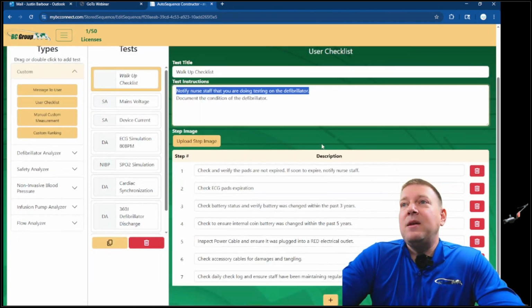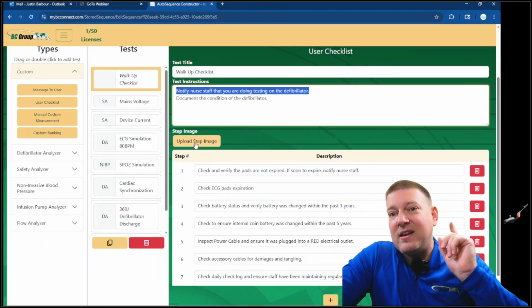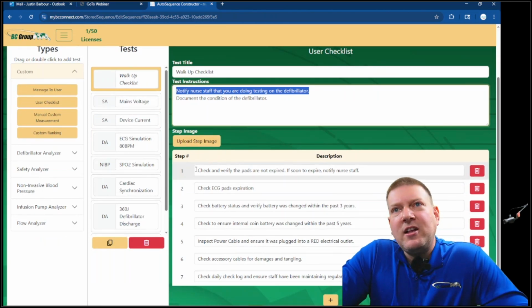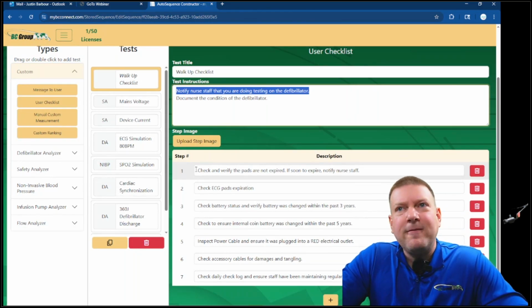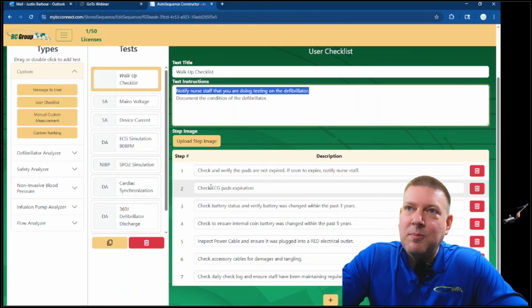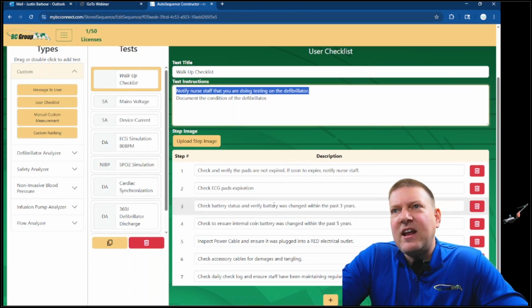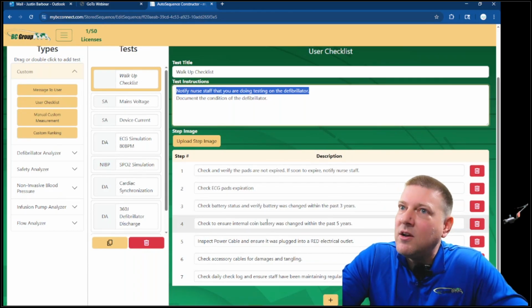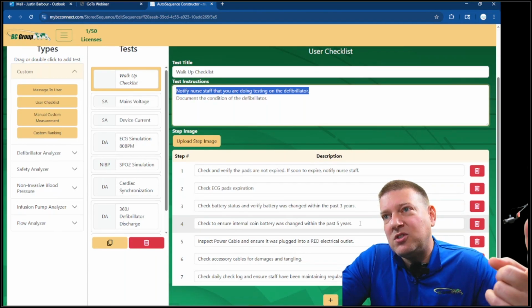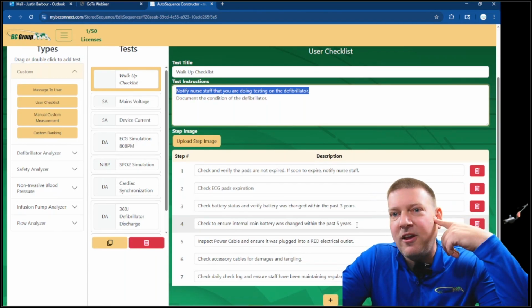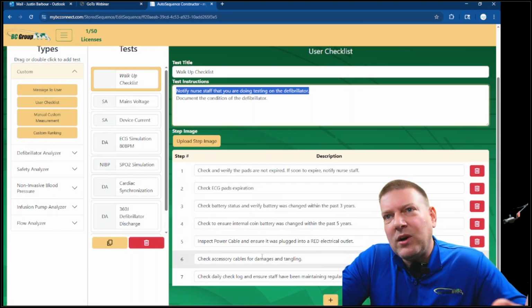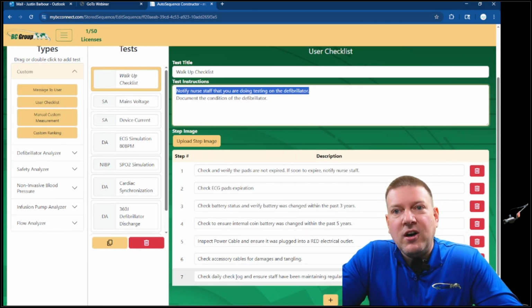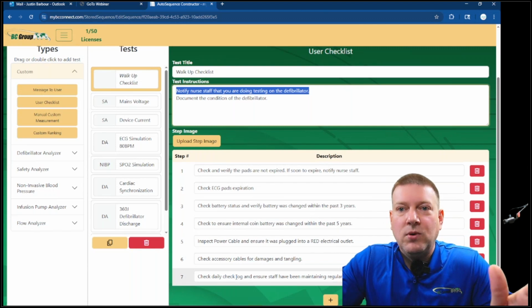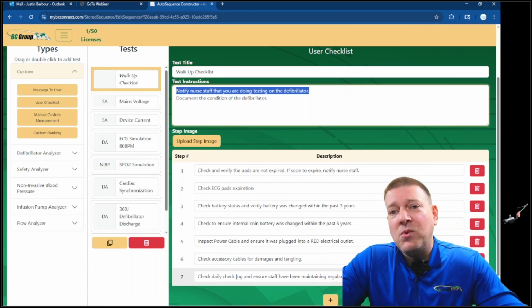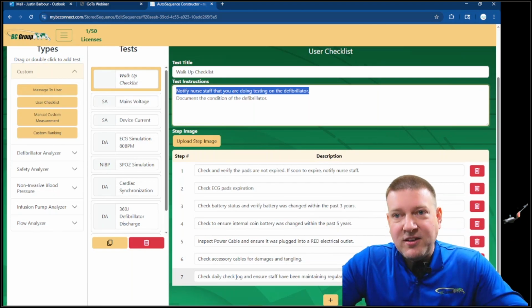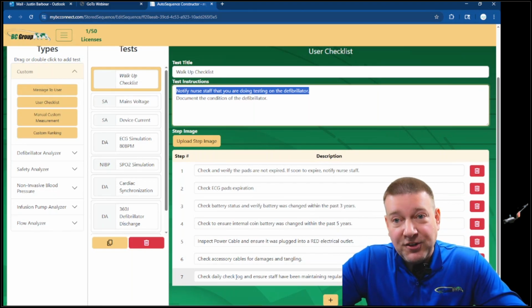Pretty easy. Then we have a checklist down here where I can incorporate images. So, general checklist for a walk-up of a defibrillator: check and verify pads are not expired, check the ECG pad expiration, check the battery status and verify the battery was changed in the last 3 years, check to ensure the internal coin battery was changed in the last 5 years. By the way, this is for a LifePak 20. Inspect the power cable, check accessory cables, generic things you should automatically do when you walk up to a defibrillator. If any one of these is wrong, you should automatically stop the test, and there's no sense continuing until it's remedied.